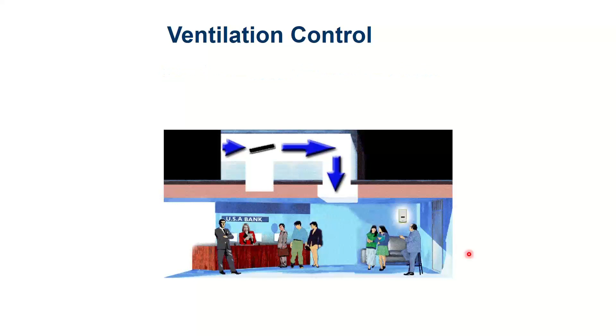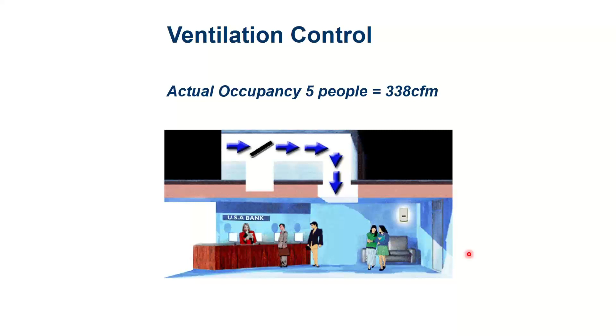Okay, so I got the occupied space, fully designed, 25 people, 488 CFM for my little bank. If only 5 people are there, I'll throttle it back to 338. I'm going to modulate the per person number, but not the square footage number. The 0.06 stays the same, the 7.5 per person gets modulated down. And then when she's by herself, I'm down to 308 because I've got the square footage plus 1 person at 7.5. So I was able to modulate from 488 down to 308. That's a 180 difference—doesn't sound like a big deal, but that's half a ton of cooling. That's going to save me some decent amount of energy.